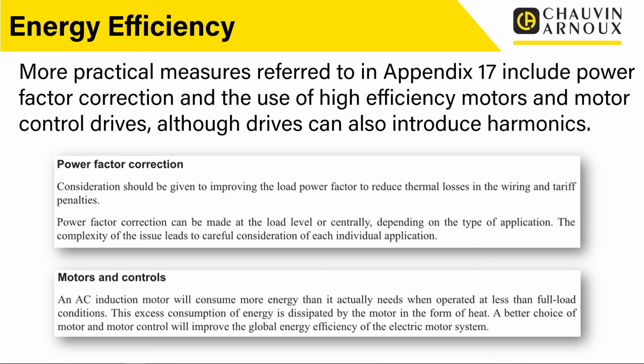We've recently seen examples where we've been out to site and actually seen 20, 30-year-old power factor correction equipment still in operation, that was designed to correct the power factor for motors that have long since disappeared. And there's now drives there, there's new motors, but the power factor correction is still there. And in that case, obviously, that's having a detrimental effect.